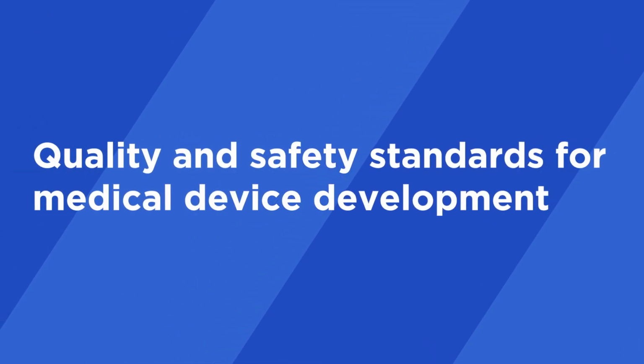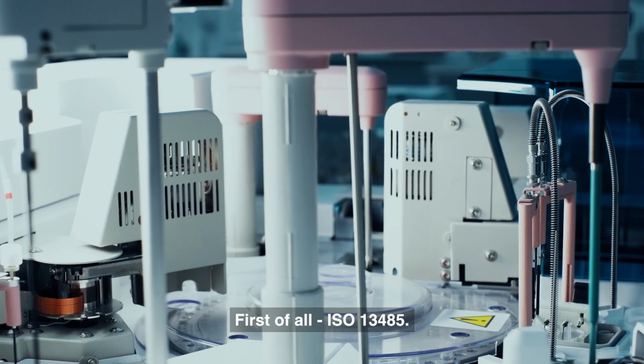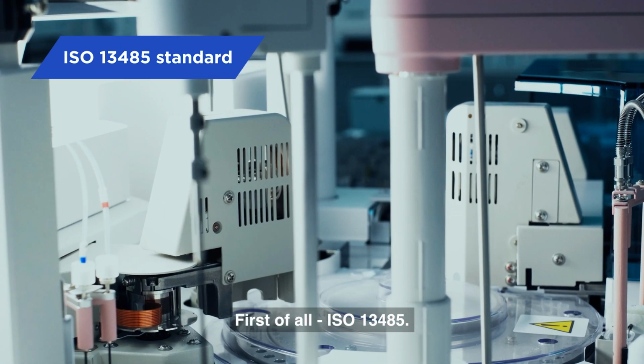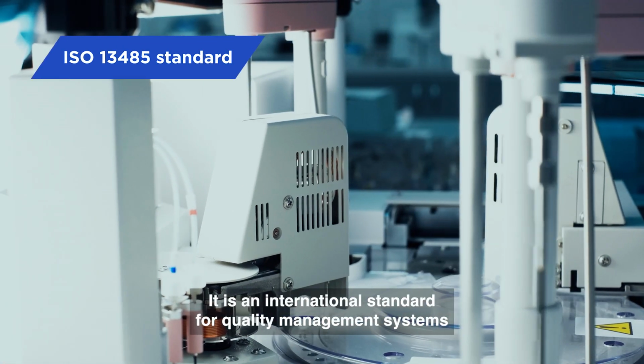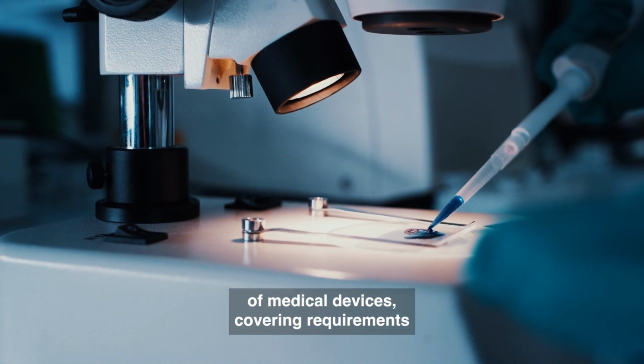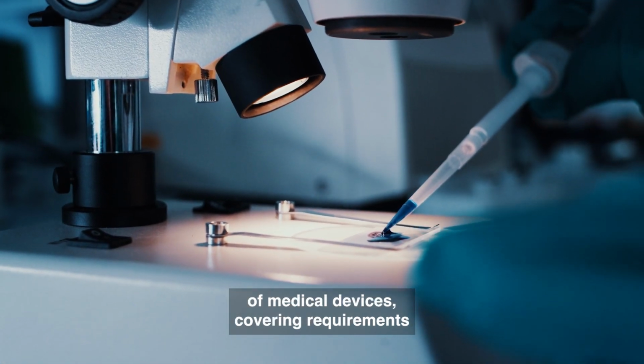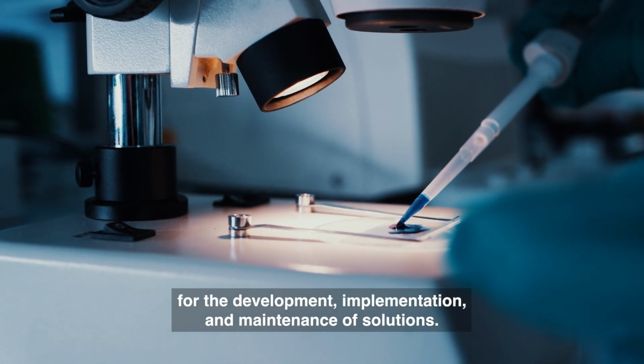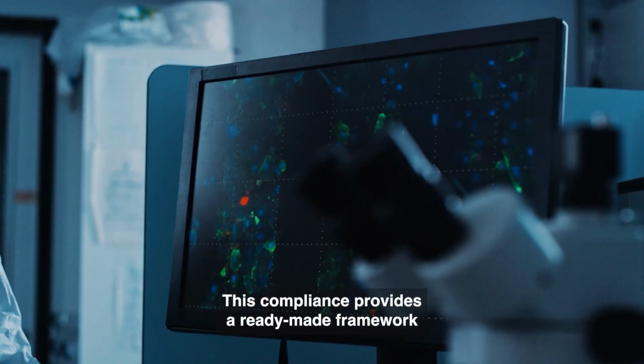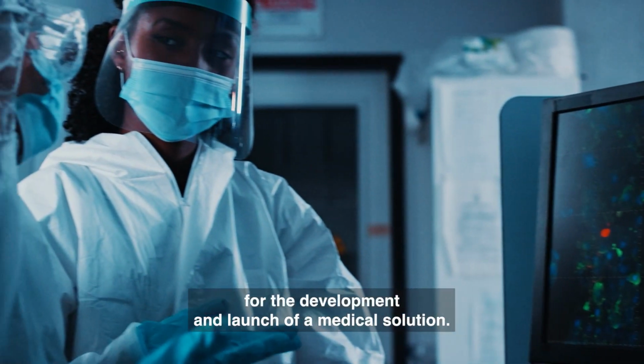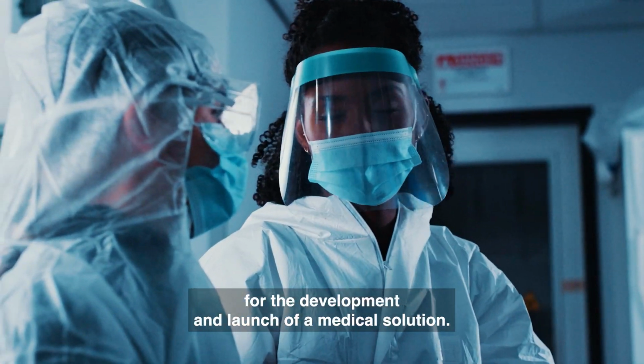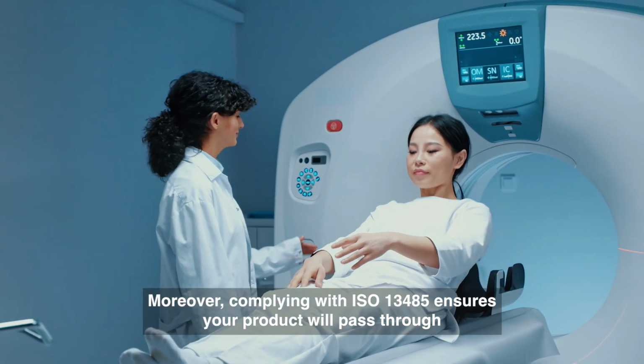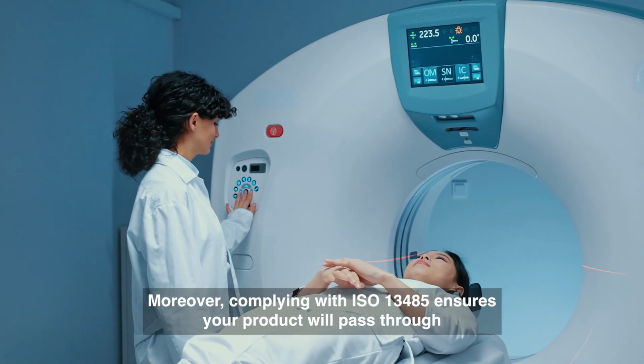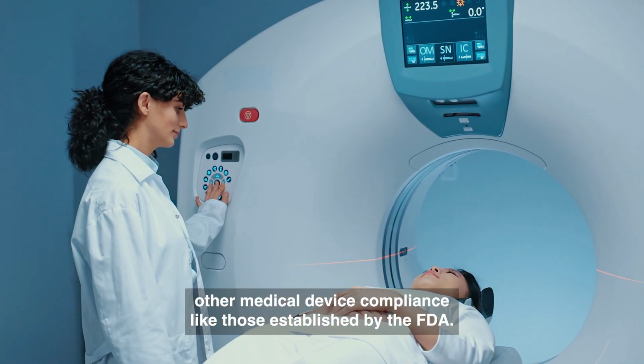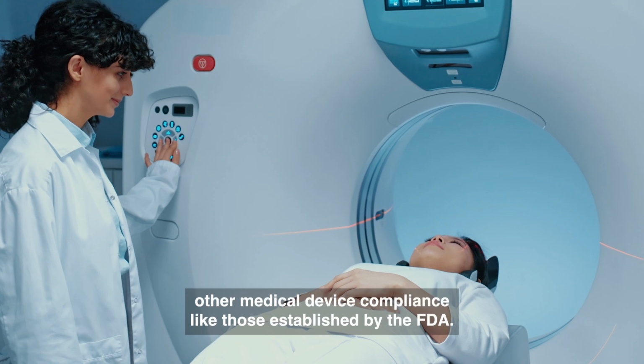What quality and safety standards must medical device development adhere to? First of all, ISO 13485. It is an international standard for quality management systems of medical devices, covering requirements for the development, implementation, and maintenance of solutions. This compliance provides a ready-made framework for the development and launch of a medical solution. Moreover, complying with ISO 13485 ensures your product will pass through other medical device compliance, like those established by the FDA.